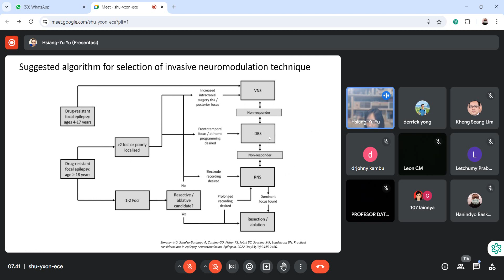And care after implantation or programming. For the VNS, you can see how LivaNova provides the table and the protocol. There is just a suggestion on how to titrate the dosage of this stimulation. But usually it is better to wait for 2 weeks after the implantation, because you need time to let the electrode fix well, and after the tissue reaction subsides, the impedance will be more stable. At that time, you start stimulation, it will give better control and the patient will feel better.